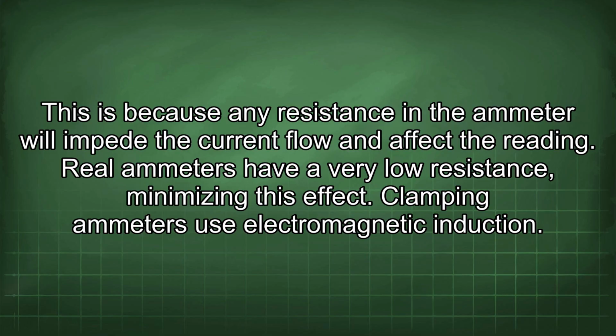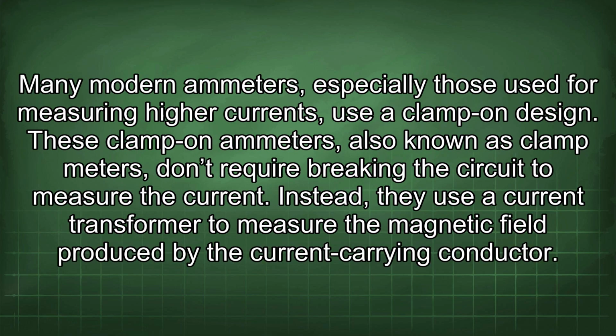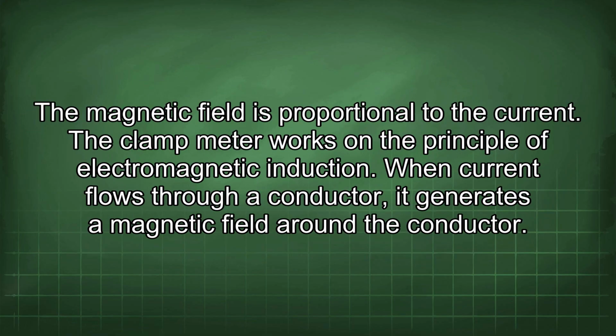Clamping ammeters use electromagnetic induction. Many modern ammeters, especially those used for measuring high currents, use a clamp-on design. These clamp-on ammeters, also known as clamp meters, don't require breaking the circuit to measure the current. Instead, they use a current transformer to measure the magnetic field produced by the current-carrying conductor. The magnetic field is proportional to the current.